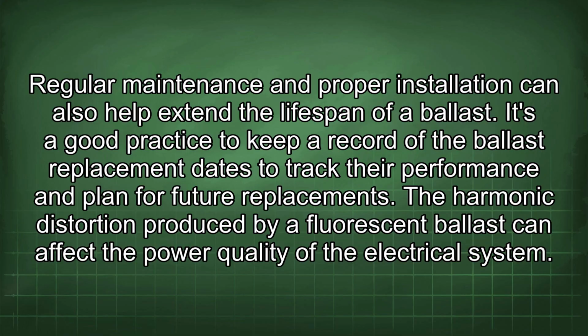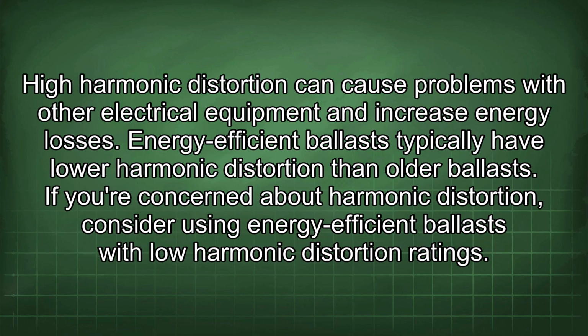The harmonic distortion produced by a fluorescent ballast can affect the power quality of the electrical system. High harmonic distortion can cause problems with other electrical equipment and increase energy losses. Energy-efficient ballasts typically have lower harmonic distortion than older ballasts. If you're concerned about harmonic distortion, consider using energy-efficient ballasts with low harmonic distortion ratings.